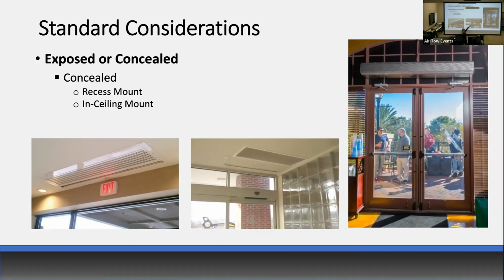There is a rule of thumb that for every inch you go above the door header, you need to move that air curtain out a half an inch. So let's say this is 12 inches. You would need to move that air curtain nozzle out 6 inches up at the ceiling. Very important for performance. If you try to mount it directly up against the wall, it leaves at an angle, so it's going to hit that glass transom and bounce right back in, and you've lost the protection over your opening. So if we get a call that an air curtain's not working, typically we would ask for a picture of the install, and something might need to be tweaked with this.